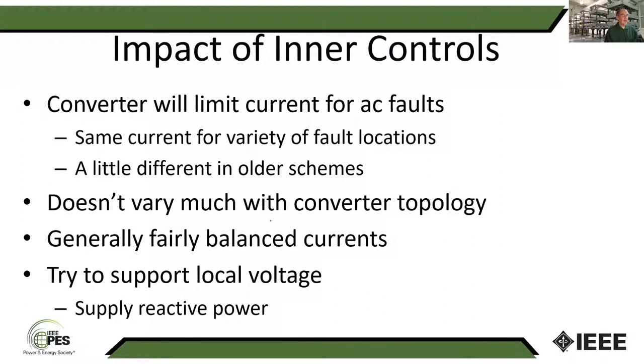And so it means that if there are AC faults, this is going to limit the fault current. So the fault current could be right at the terminals of the converter. It could be 5 kilometers away or 10 kilometers or whatever, and it's going to be about the same fault current. Older schemes were a little bit different, but most of the modern schemes use this. And generally they're controlled so they produce fairly balanced currents, so you don't see much negative sequence. Some vendors trying to meet local grid codes are being asked to produce negative sequence currents. They don't always get the phase angle of that right, so it can also cause problems.